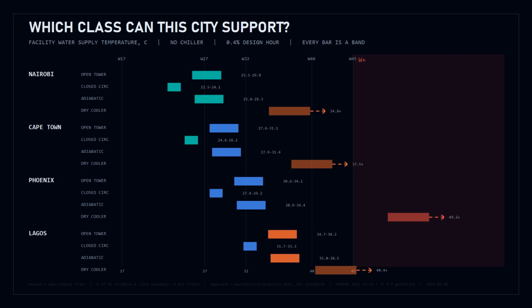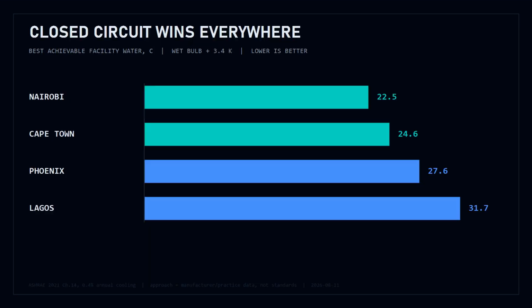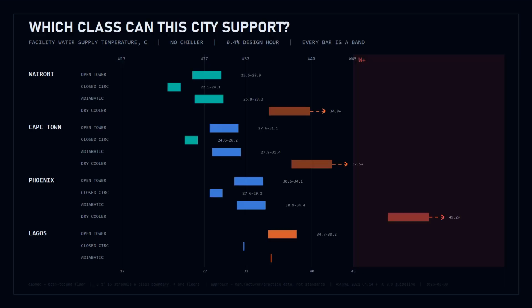Closed circuit does better everywhere because you have deleted the heat exchanger. Nairobi and Cape Town to W27, Phoenix to W32, Lagos straddling W32. Dry coolers. All 4 of these are floors, not classes. This class or worse with no ceiling. Nairobi, W40 or worse. Lagos lands at 40.4 degrees. That is 0.4 of a degree over the W40 ceiling, which is inside the rounding of every number that went into it. I am calling that a tie.